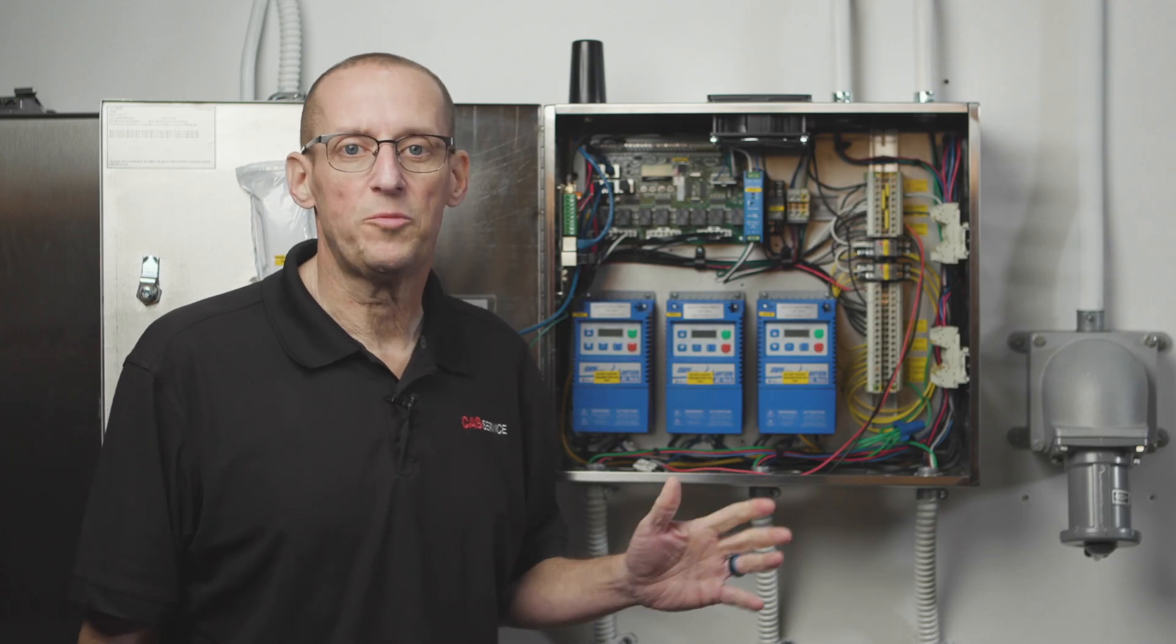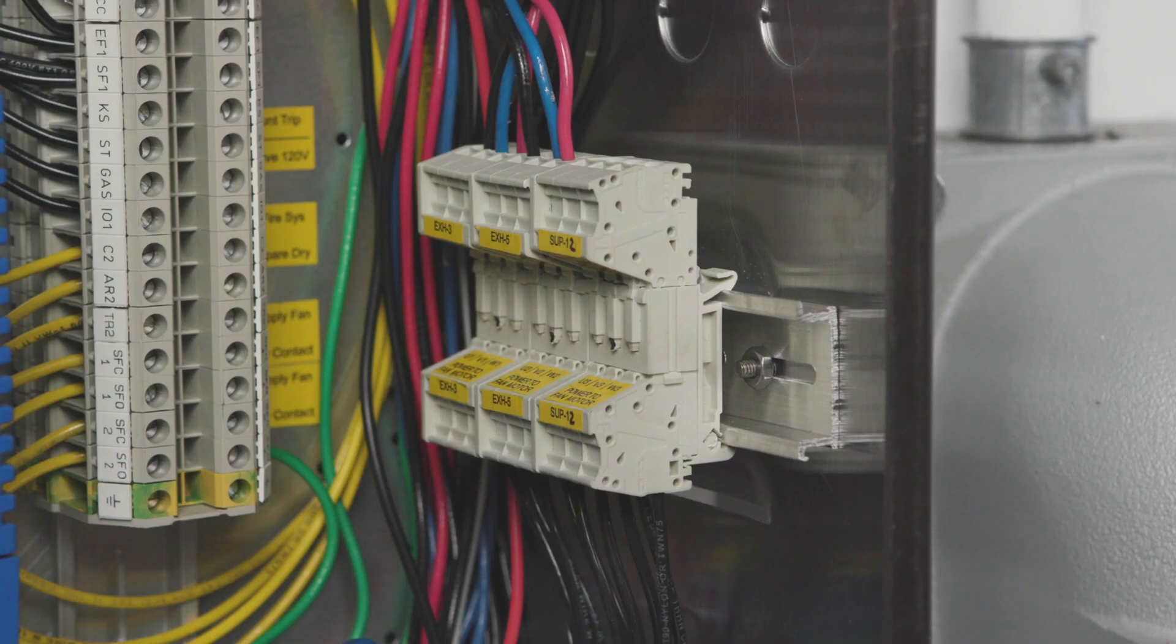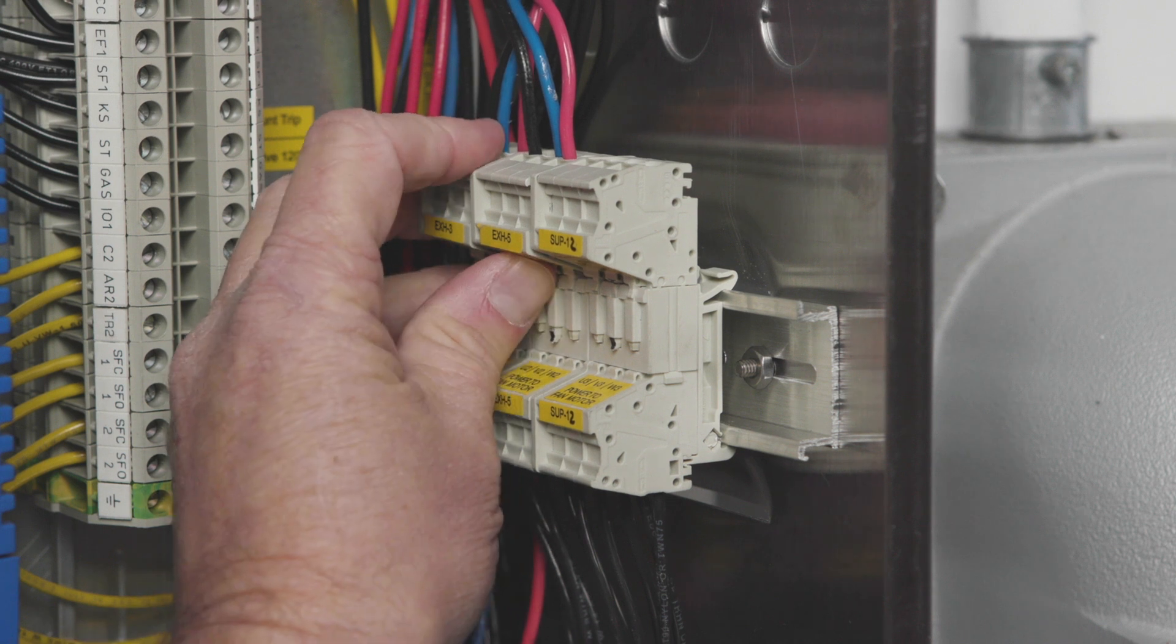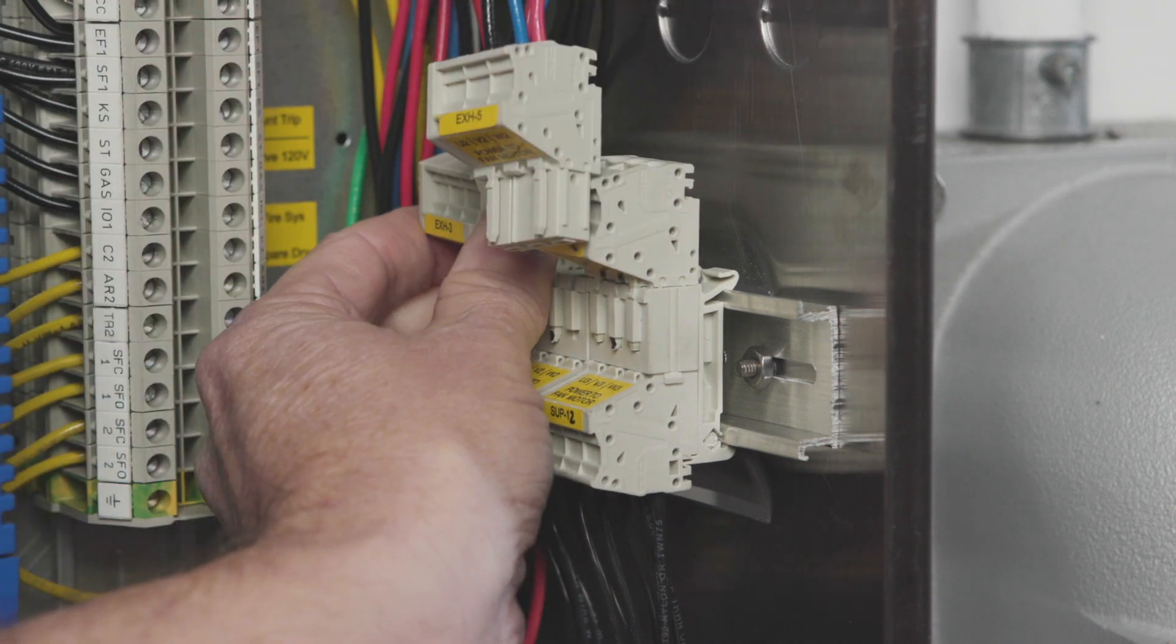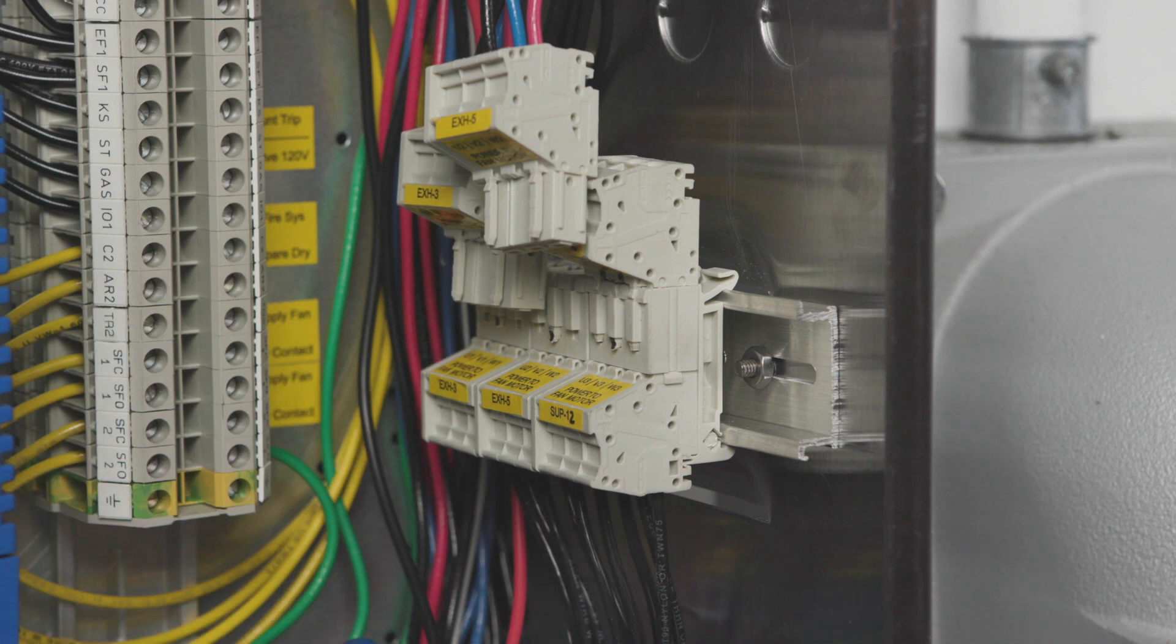So first, if your control package has VFDs, what you want to do is we want to unplug these quick disconnects here. This is the load power from the VFD to the fan. What this does is it protects the VFD should you get it miswired.